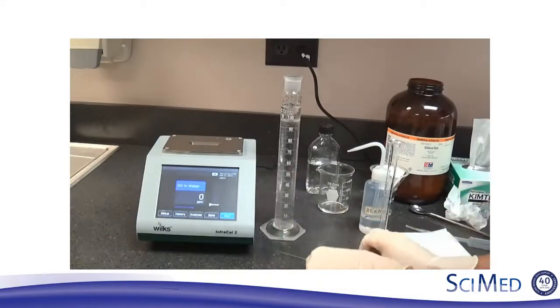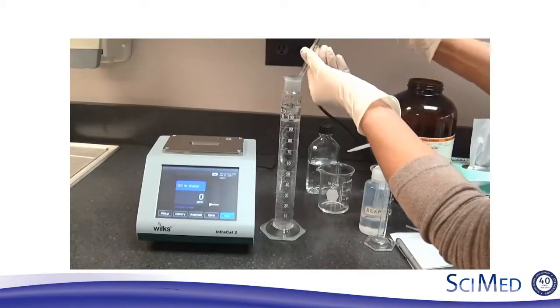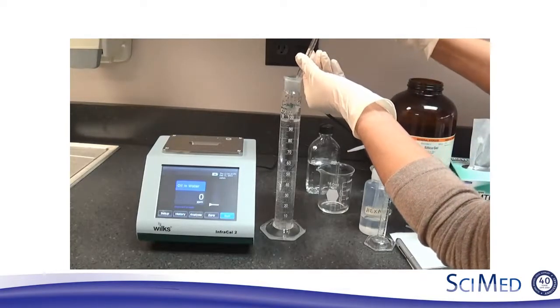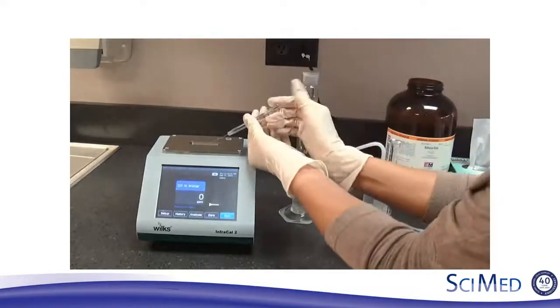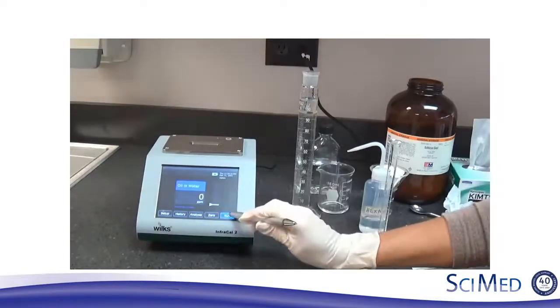The sample's shaken up, and then we take 60 microlitres and deposit that onto the top of the instrument. Because the instrument lays flat, that forms a nice steady film and the hexane evaporates away. This whole video is on YouTube — just Google 'InfraCal YouTube' and it'll come up as the first hit. We'll happily come and do demonstrations, and we'll happily accept samples from you. If there's a question you'd like to ask offline, please do get in touch. Thank you.